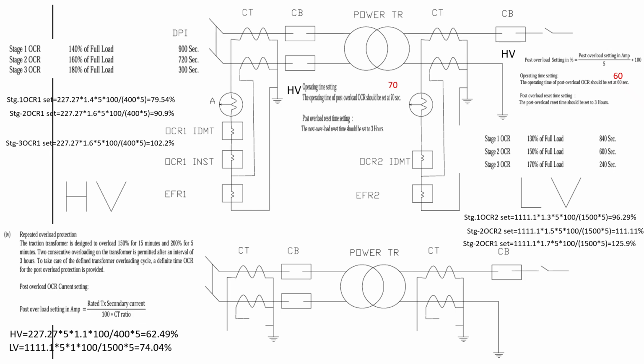Okay, so this is the setting for the current relays, like overcurrent and restricted earth fault. These are all the current relays. Then if you see the feeder side, there will be current and voltage relays, and in transformer protection we have taken many mechanical relays also, like PRD, pressure relief device, then warning temperature, oil temperature. I will discuss in the next 2 slides.